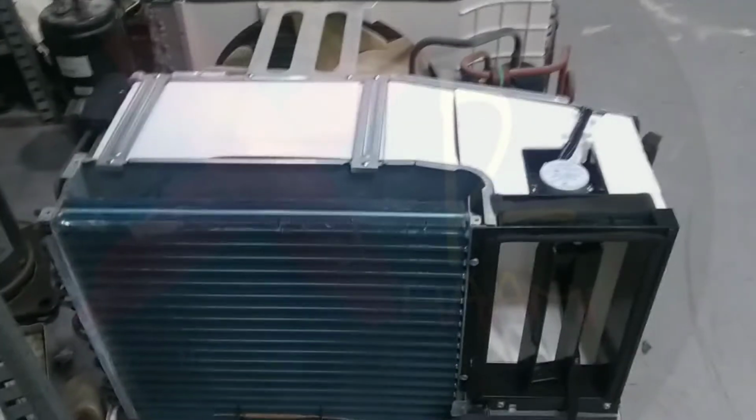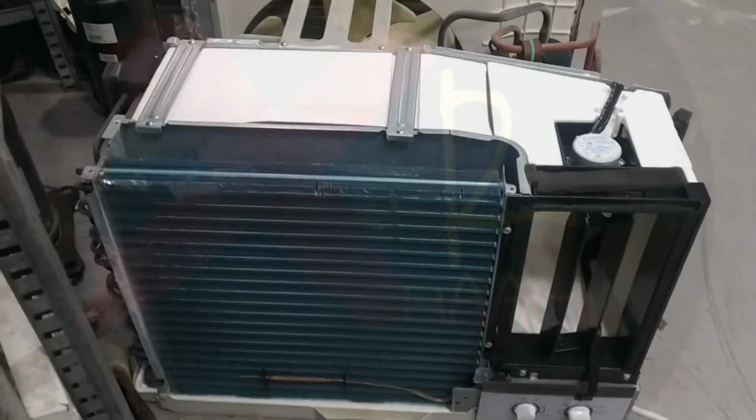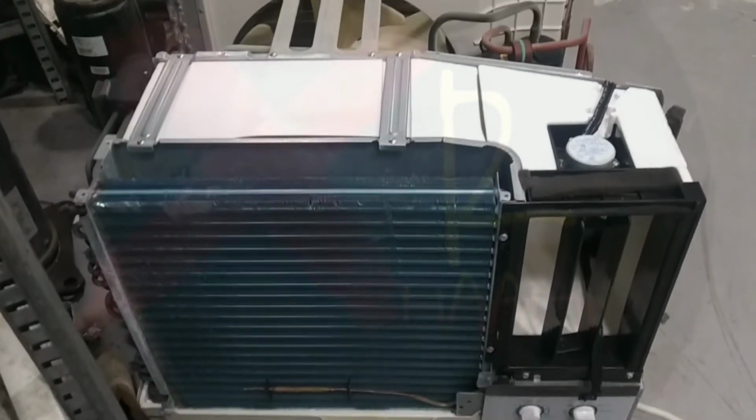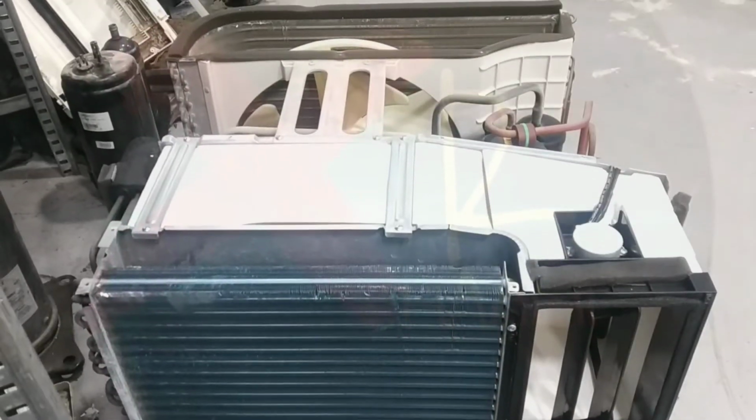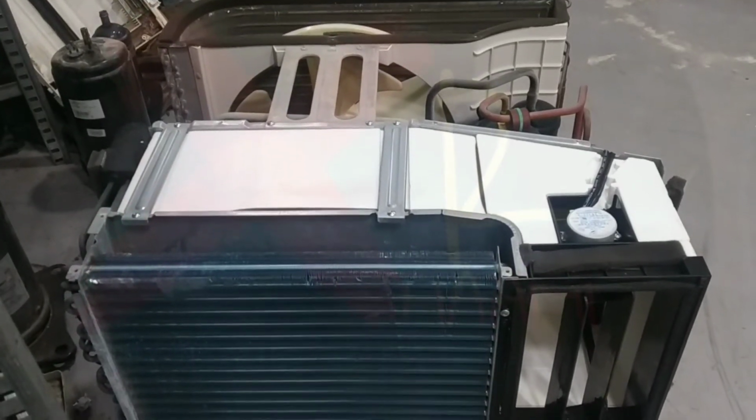So the most common cause of icing over is this. As you can see, this is the air blower. Maybe sometimes it is too dirty, and as you can see, this is the motor. Maybe your fan motor is faulty. If your fan motor does not run and airflow does not come out, you will face the icing over problem in your air conditioner. So make sure your fan motor is in good condition, and double check your capacitor also.